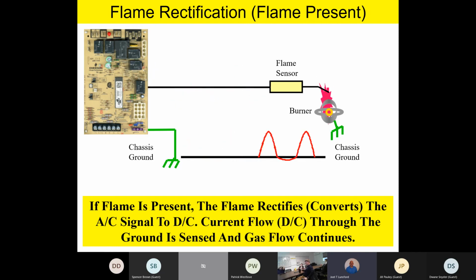And then that DC voltage that's actually provided on the chassis ground is going to be monitored by the control board. And if it senses DC voltage on the ground plane, it knows there's a flame present. And as long as it sees that, it will allow the gas to continue to flow. So that's the science behind flame rectification. We take AC voltage, run it through the flame, which rectifies it, and dumps pulsating DC along the ground plane.